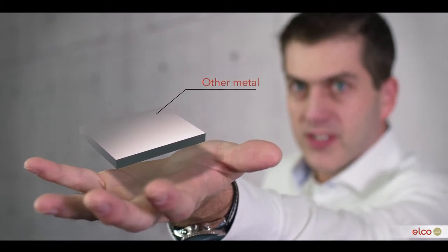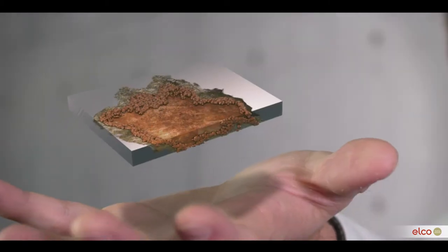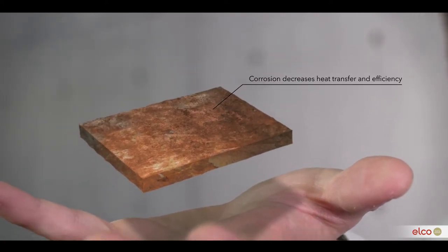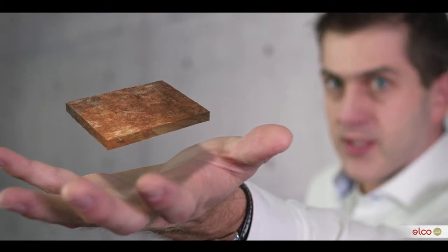However, when left in both warm and damp conditions, this layer is not resistant against the acidic attack of the condensate. The protective layer will be damaged, corrosion will progress, and both heat transfer and efficiency will decrease over time. This even can lead to heat exchanger breakdowns.